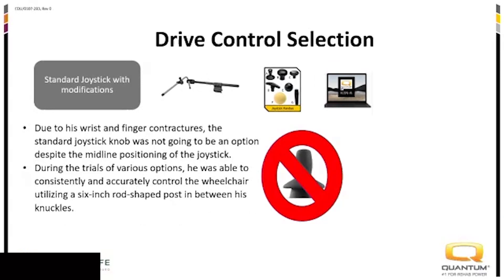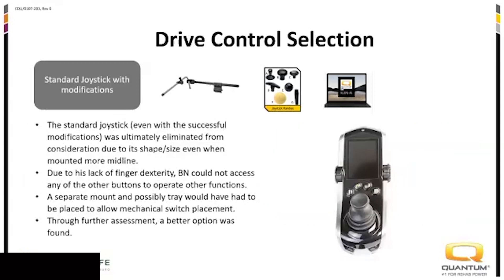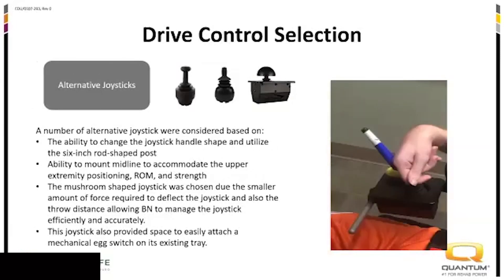The standard joystick has a lot of buttons, dials, and speed potentiometers — it's big and bulky — so it wasn't ideal to put midline, especially since he couldn't access any of those buttons or toggles anyway. We tried a couple of different alternative joystick types and eventually ended up utilizing a mushroom-type joystick. We could take the mushroom part off and put that six-inch thin rod on that joystick. It had less force requirement to activate, and it also had a kind of built-in tray — which was important for the next step.